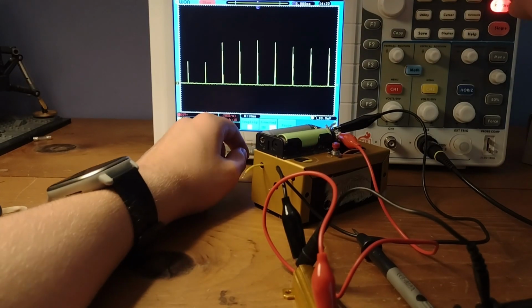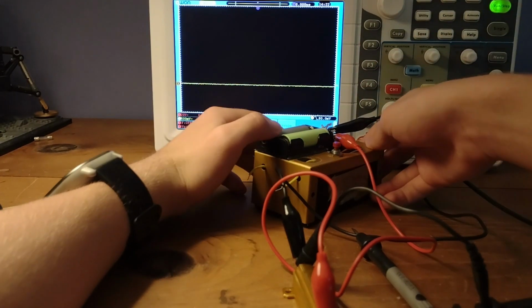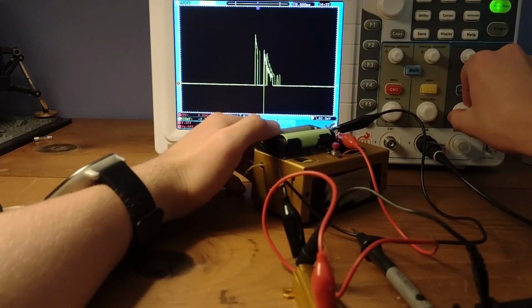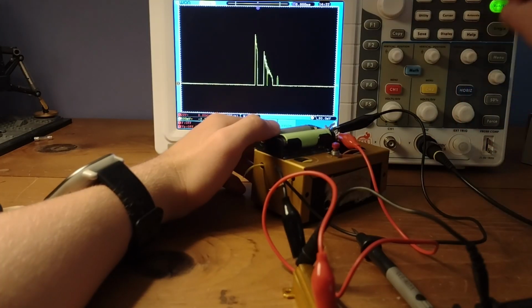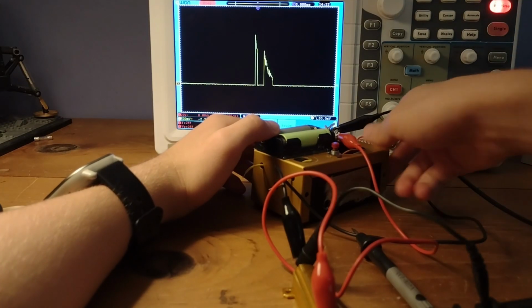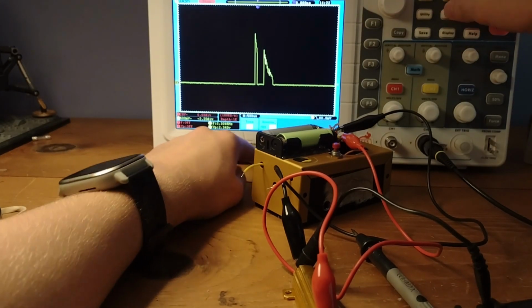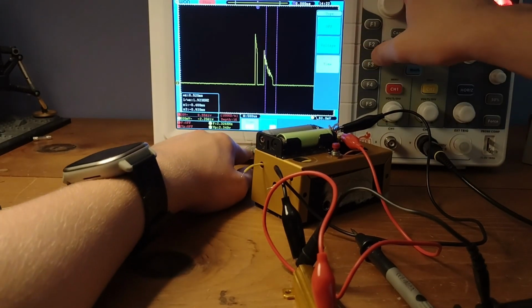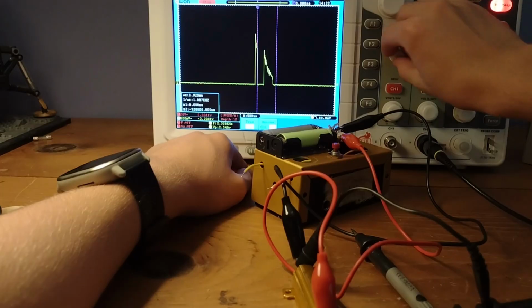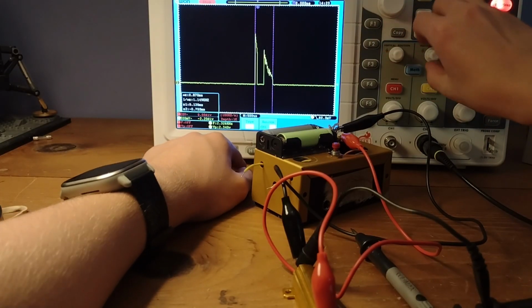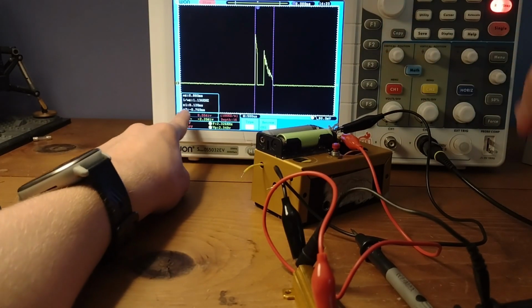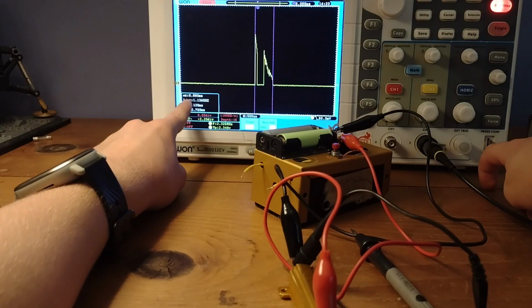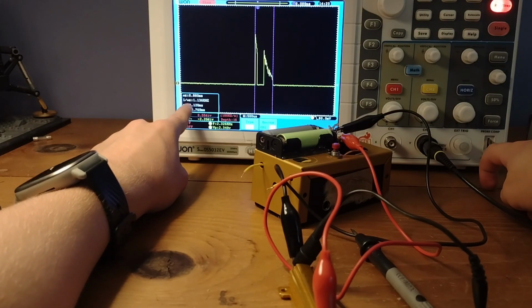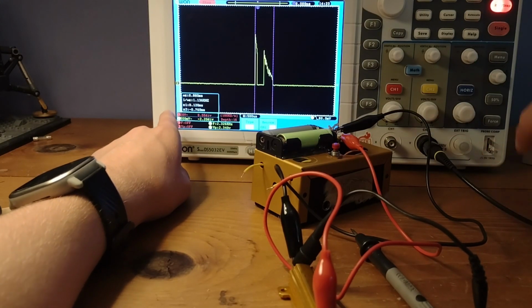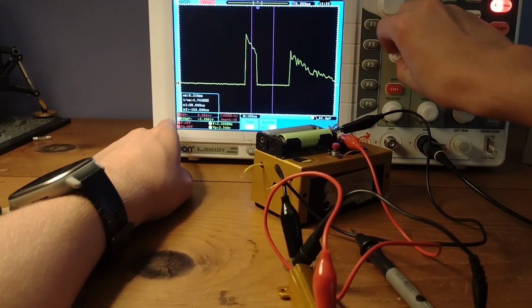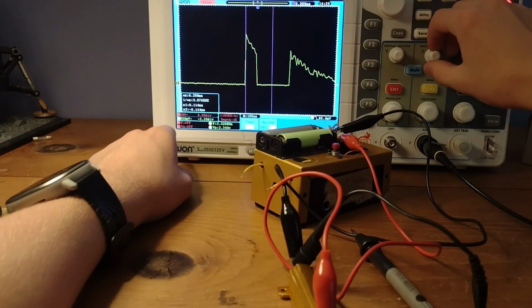Let's try to measure the duration of those pulses. Here is the pulse. Let's put the cursor on the time mode to measure the distance between the maximum peaks, and the entire pulse lasts for about 0.88 milliseconds, or 880 microseconds, and the actual high current part of the pulse, where it exceeds 1 amp, is just 114 microseconds.